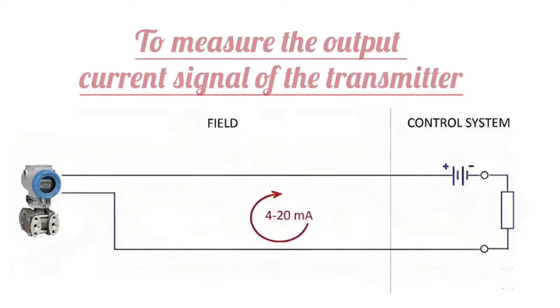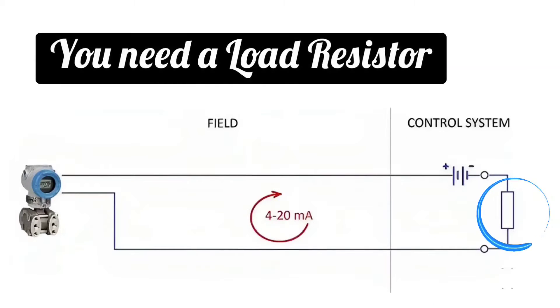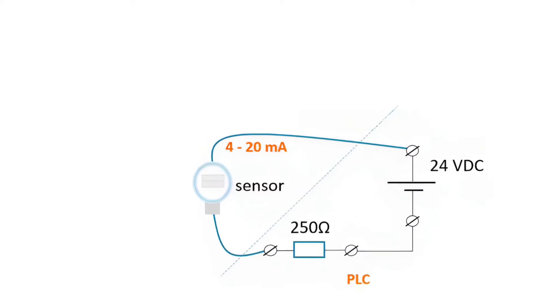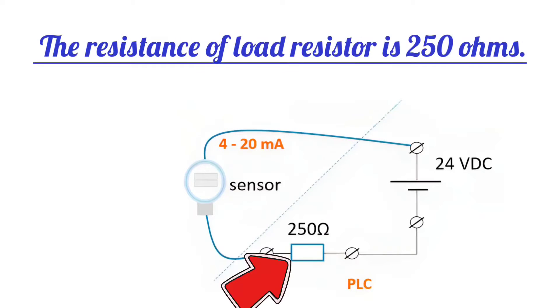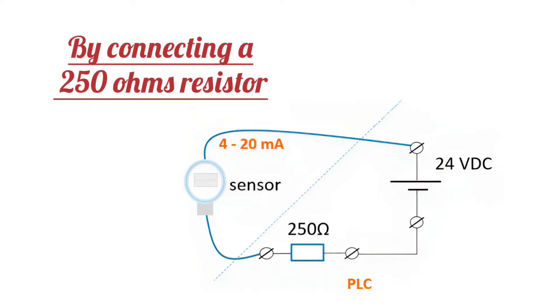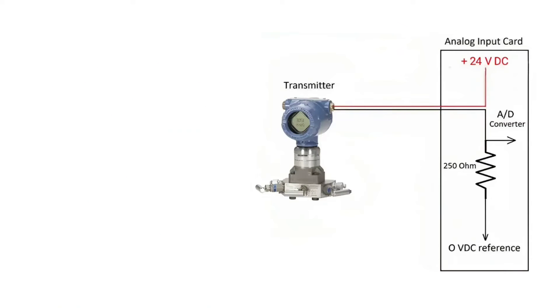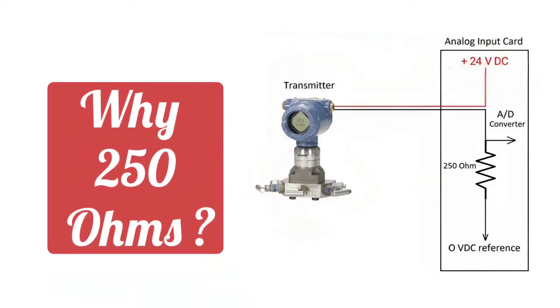To measure the output current signal of the transmitter, you need a load resistor. The resistance of the load resistor is 250 ohms. By connecting a 250 ohm resistor, the current in the current loop can be measured. Now the question arises: why is it 250 ohms?